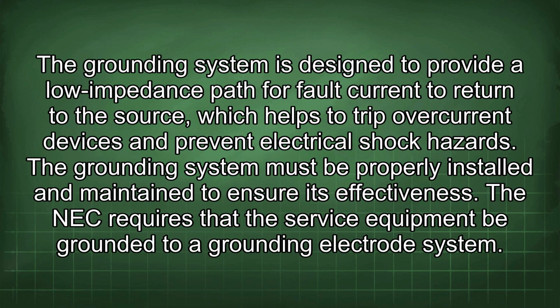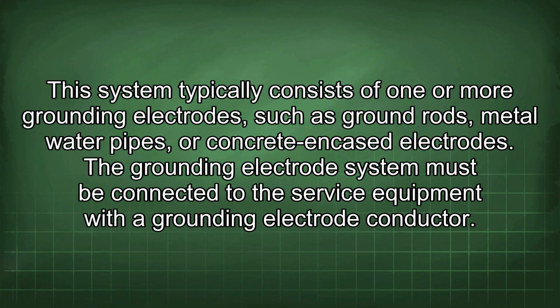The grounding system is designed to provide a low impedance path for fault current to return to the source, which helps to trip overcurrent devices and prevent electrical shock hazards. The grounding system must be properly installed and maintained to ensure its effectiveness. The NEC requires that the service equipment be grounded to a grounding electrode system. This system typically consists of one or more grounding electrodes, such as ground rods, metal water pipes, or concrete encased electrodes.